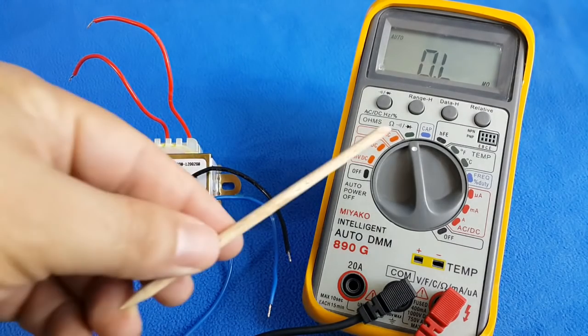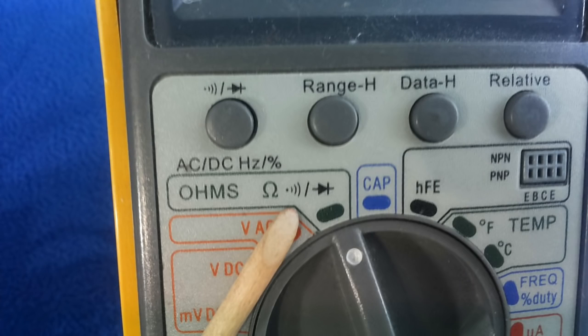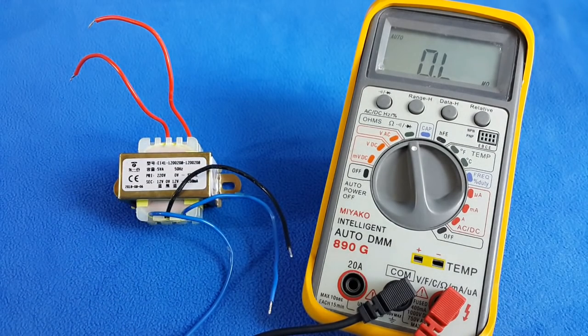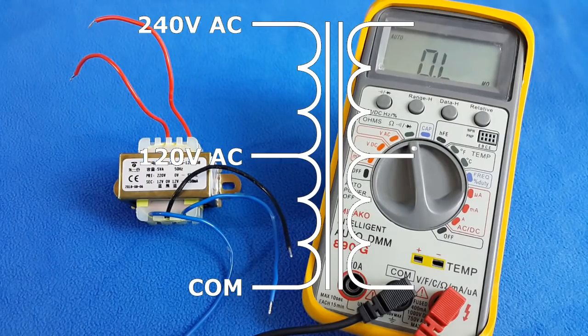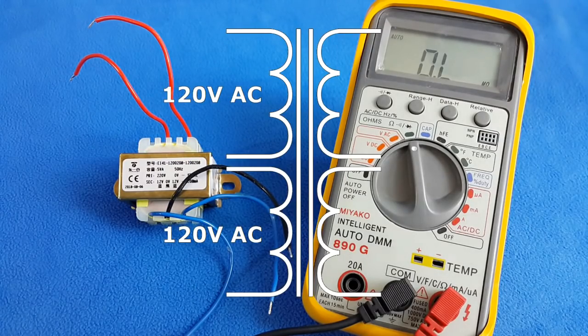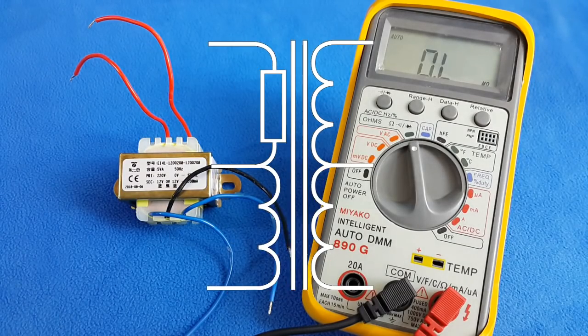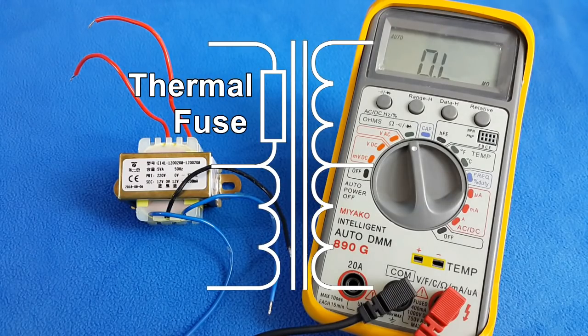Most of the time in a step-down transformer, the primary is the winding with the higher resistance, and the secondary has very low resistance, almost like a kind of short circuit. So set up your digital multimeter in ohms. We have the primary with 2 wires or even 3 wires. Those 3 wires could be 2 are the main line, 120 to 240. Other could be a center tap when we have transformers for 2 120s, or even it could be a line for a fuse.